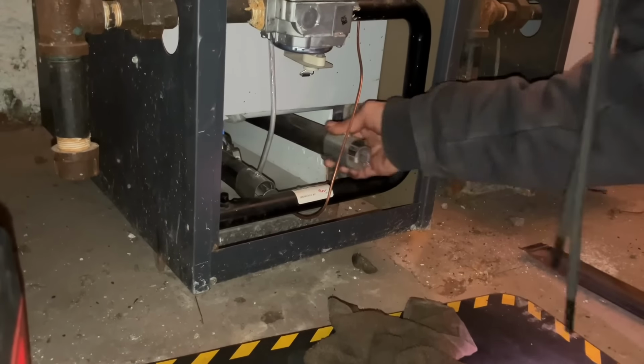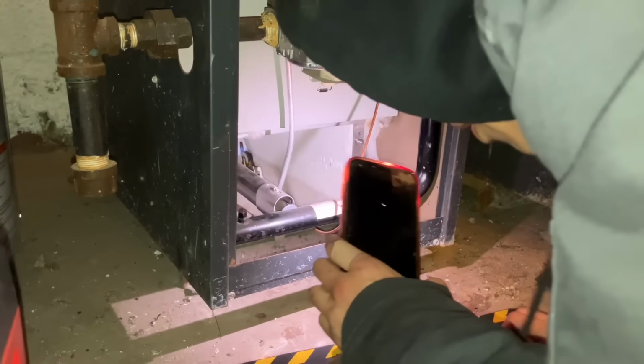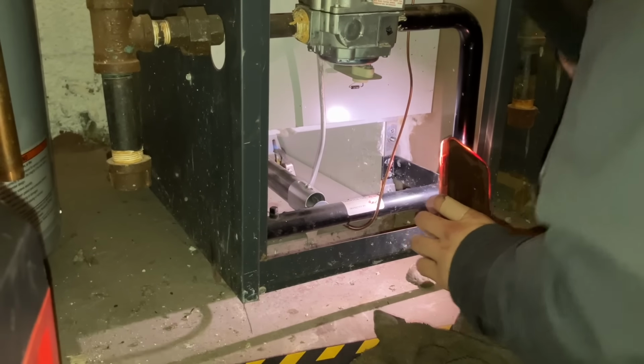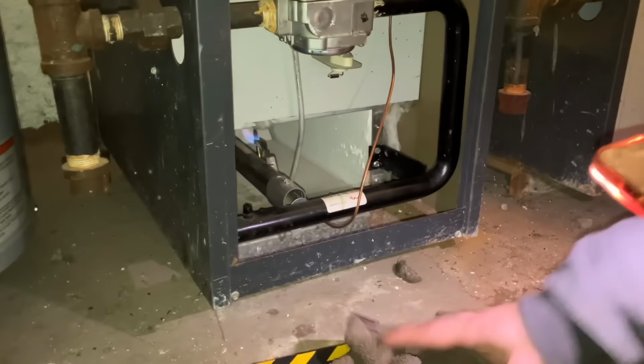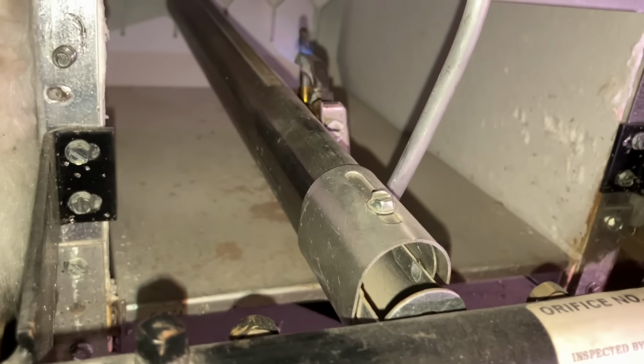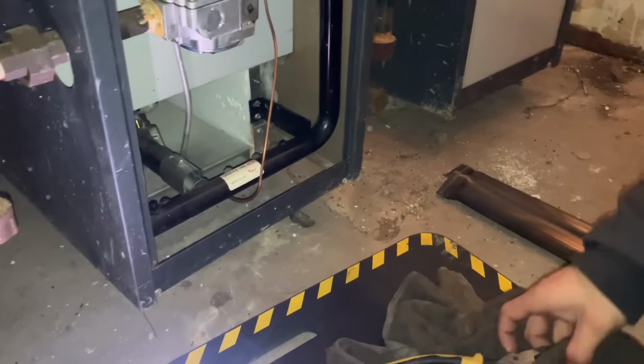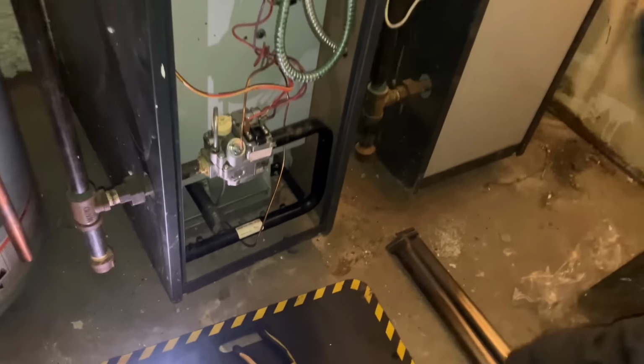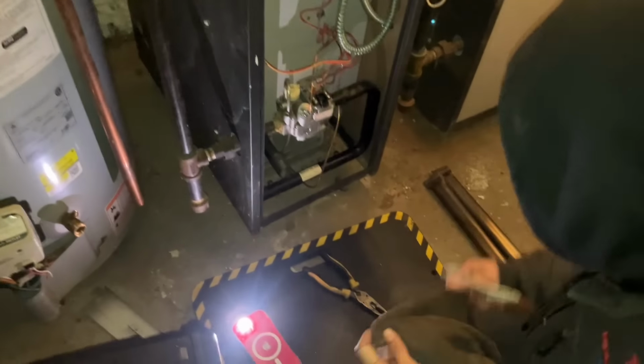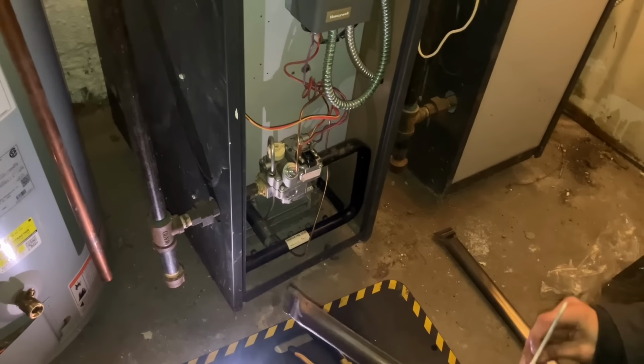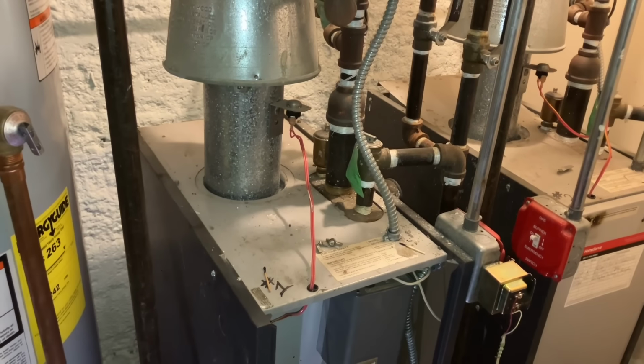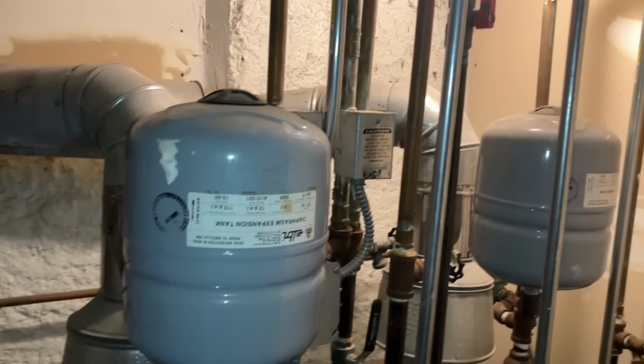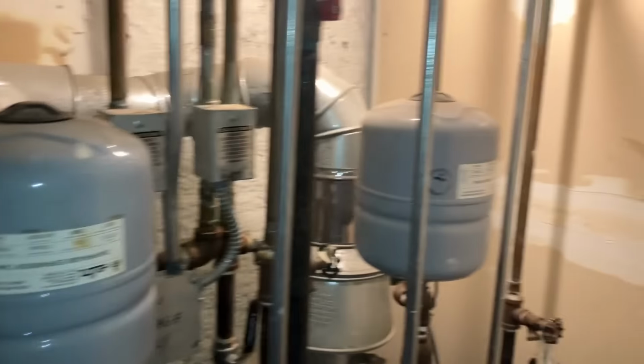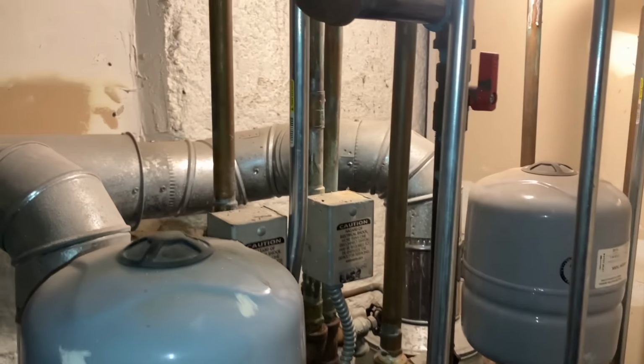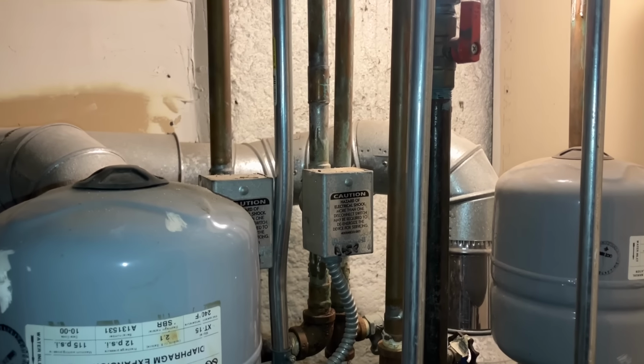Want me to take the pilot burner out too? How's it look? It doesn't look that bad. Okay. And how's the combustion chamber look? It's pretty clean. Yeah, it does look pretty clean. All right, brush down the burners with a little wire brush. Clear them off with the WD-40, spray them down, and then put everything back together, and we'll do an external cleaning of the first floor, which has those 2 zone valves. And then we'll check everything else out. Taking a look at this second floor boiler. A little bit of back pitch going on right there with that 5-inch flue pipe going to the 6. And then carrying on.